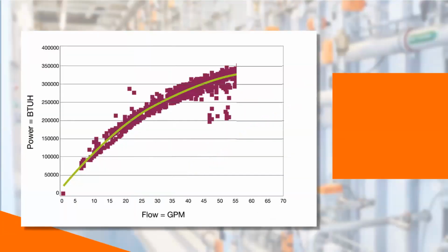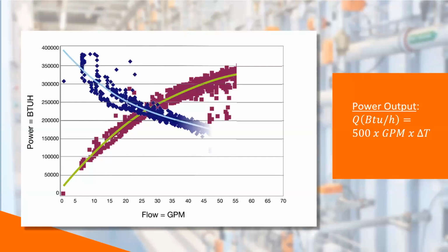Let's look at this in a coil curve with a coil point cloud. The point cloud has a thickness, and that green line is simply a best statistical fit of those points. The curve gets more shallow as the flow increases, and the BTUs at higher rates or flows are more expensive from a flow to load ratio perspective. So remember, this is our power output formula. But that power output formula also includes delta T. So if we show this delta T curve, in general, again, delta T decreases as the flow to load ratio increases.